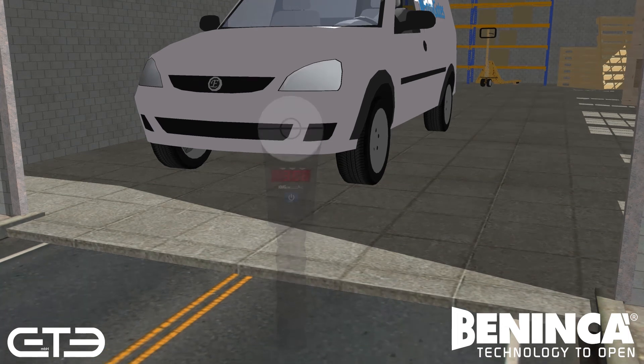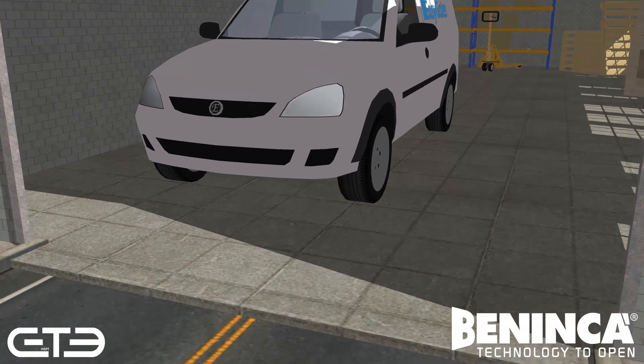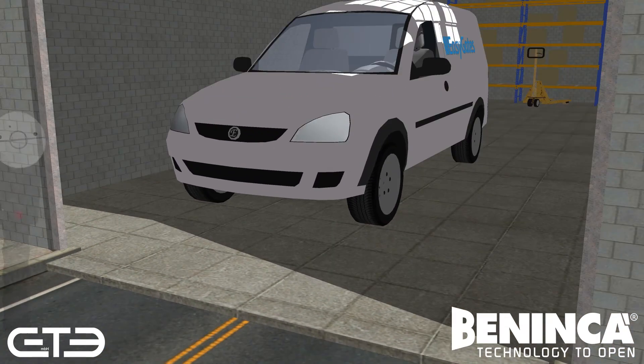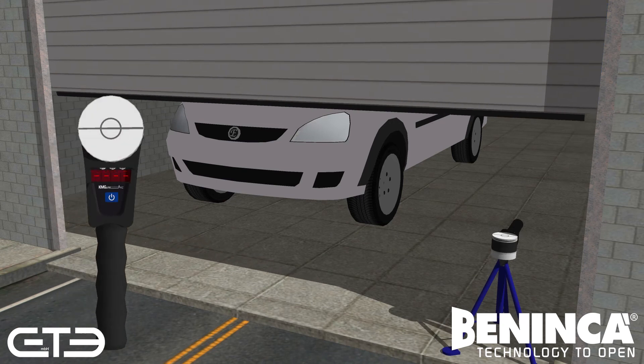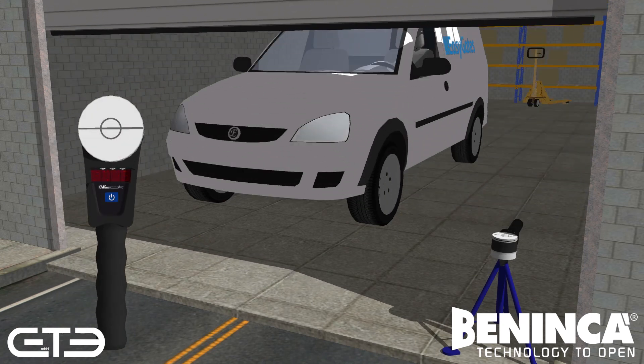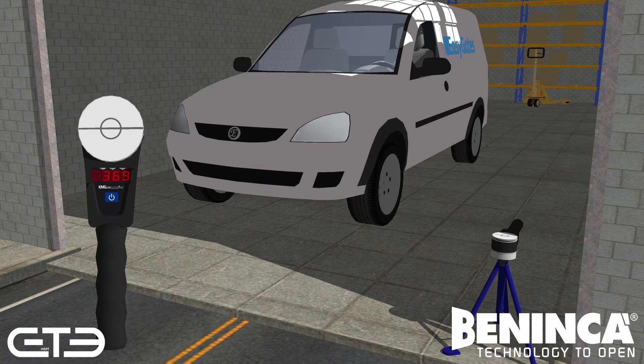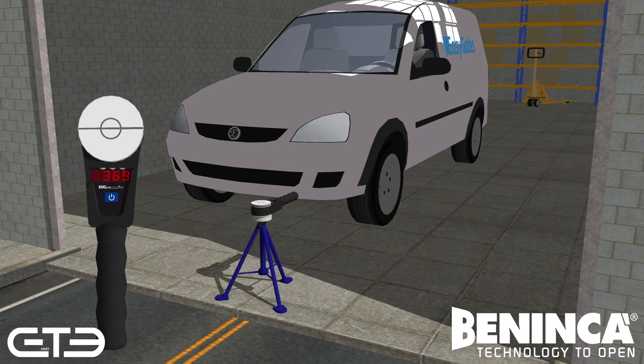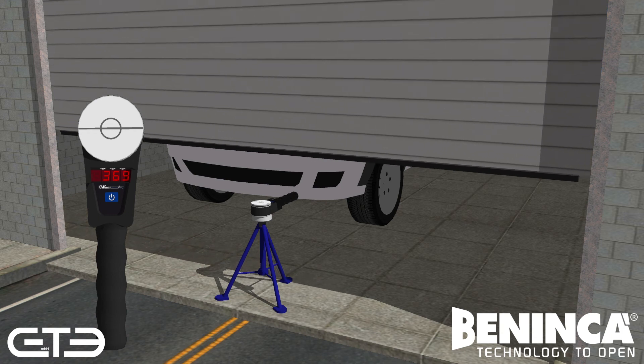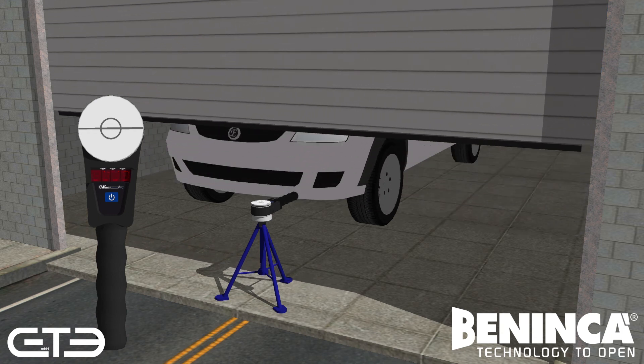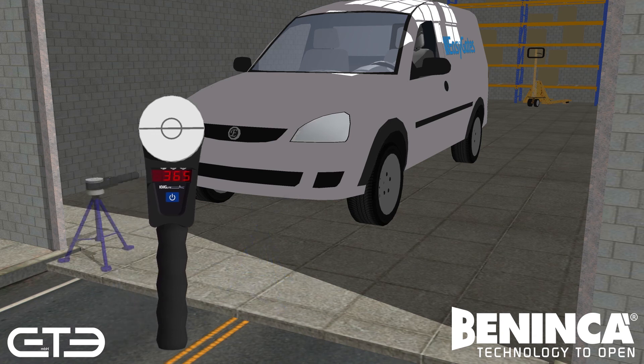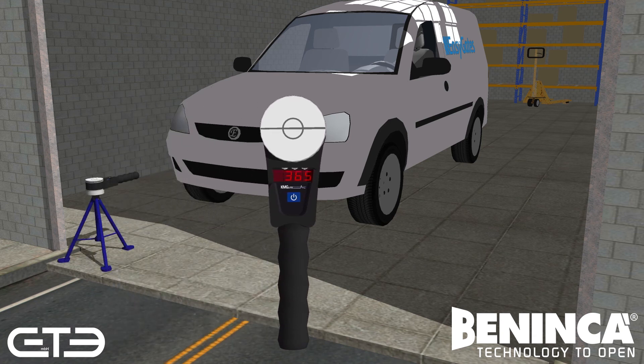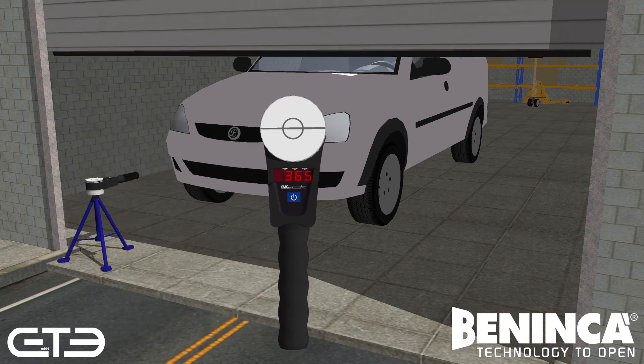For the next test, attach the tripod to the instrument and place it to take your tenth reading at 300mm up and 200mm across. Initiate the test three times and gather your results for the average. Repeat for 300mm up, halfway across, and 300mm up and 200mm across on the opposite side.